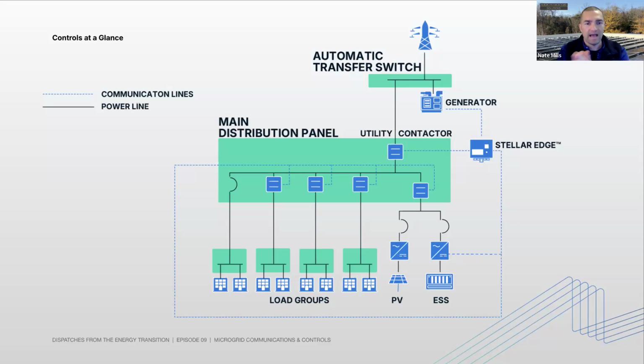And the Stellar Edge is most active when we are on grid. When we are off grid, it's making decisions about what loads can be supported based on the state of charge of the battery, how much solar is coming in, how much sun we're expected to have later in the day, the level of fuel remaining in the generator, all those sorts of things, right? So there's a lot for it to do after we make the transition to off grid, but it is not trying to power balance, right? That's the battery inverter's job. The battery inverter will be load following. It'll automatically, instantaneously respond to changes in load. That's not the Stellar Edge's job, and the control cycle is too long to enable that to happen. Okay, so that's how this system would work, going on and off grid.